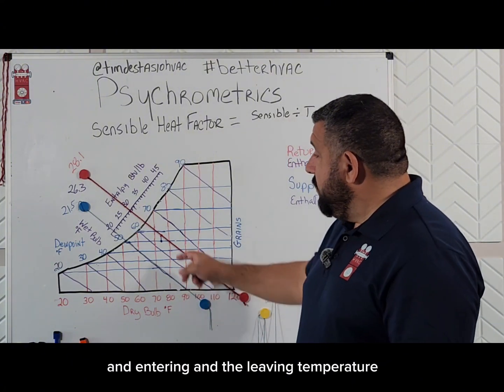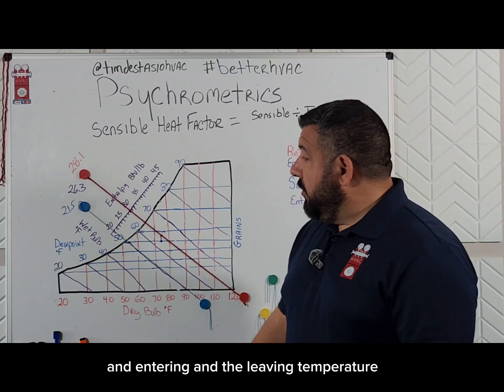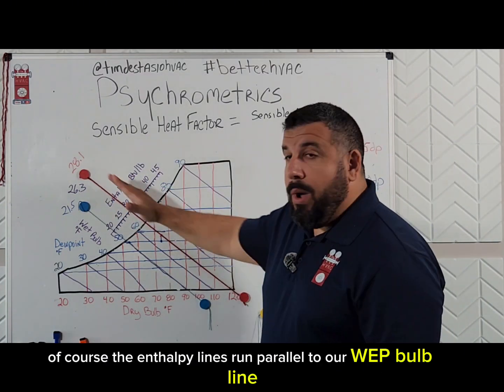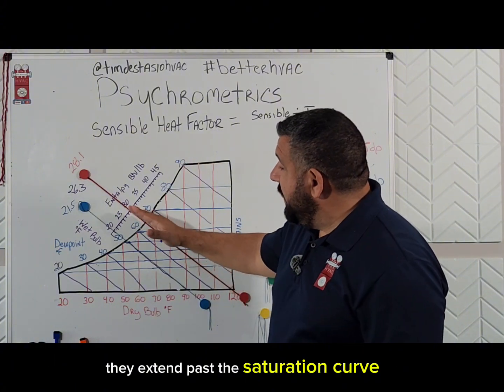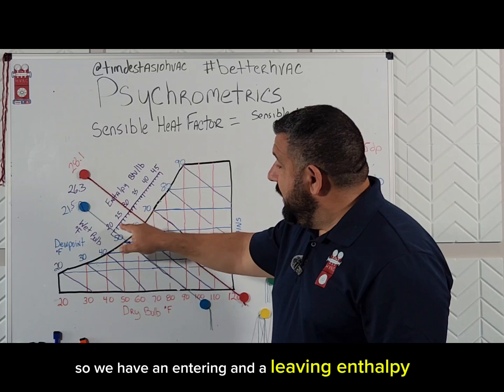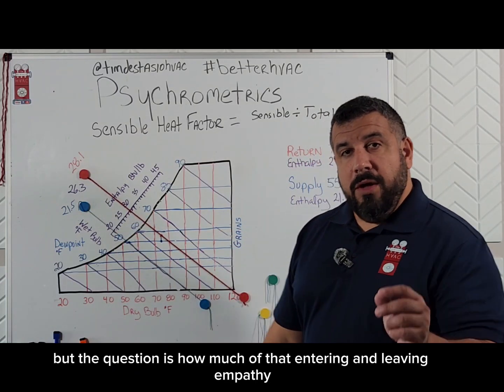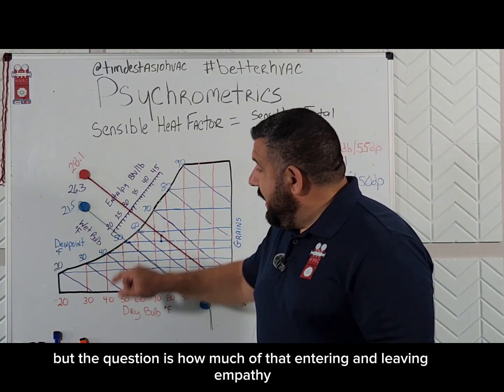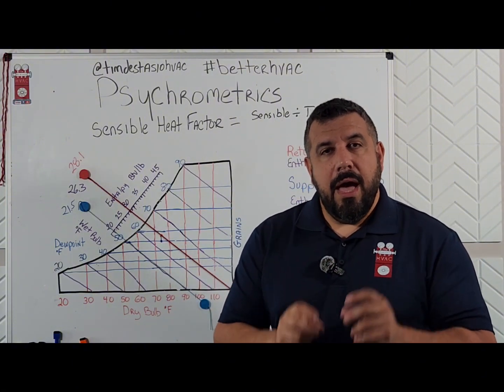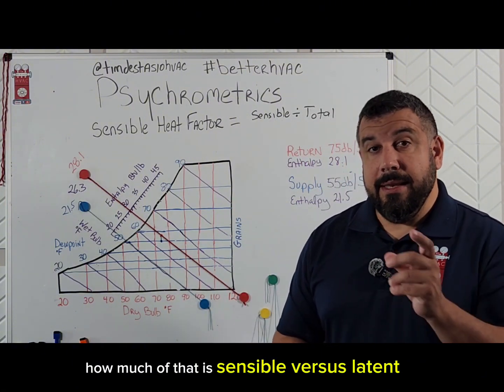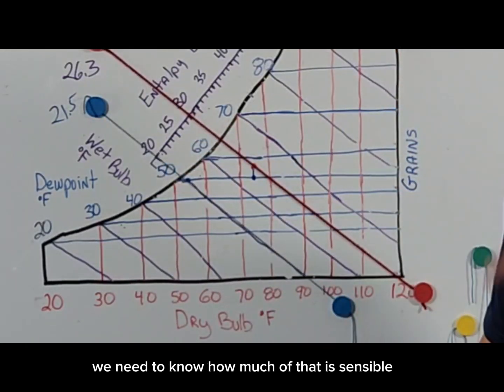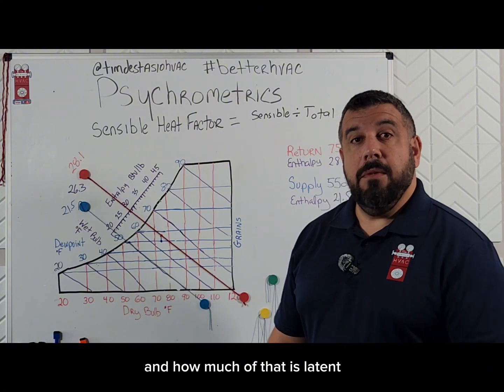Last time we plotted two points — an entering and a leaving temperature — and then we plotted our enthalpy lines. The enthalpy lines run parallel to our wet bulb lines. They extend past the saturation curve and they cross this scale right here. We have an entering and a leaving enthalpy, but the question is: how much of that difference in enthalpy that our equipment is removing is sensible versus latent?